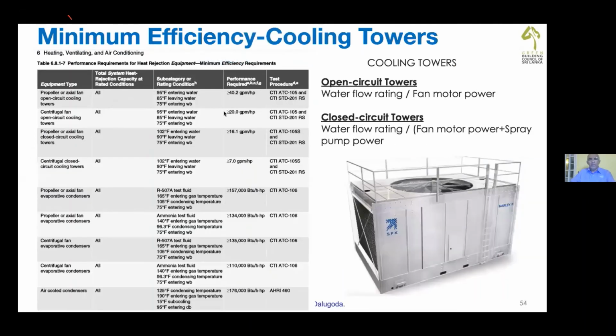Similarly, cooling towers have another measure. It is water flow rate per horsepower. Water flow rate per fan motor horsepower. And it is given here. So we'll have to comply with that. 40.2 GPM per horsepower in IP units.